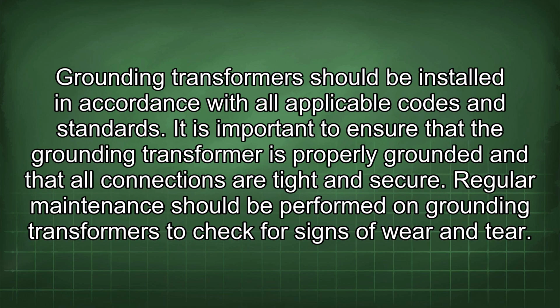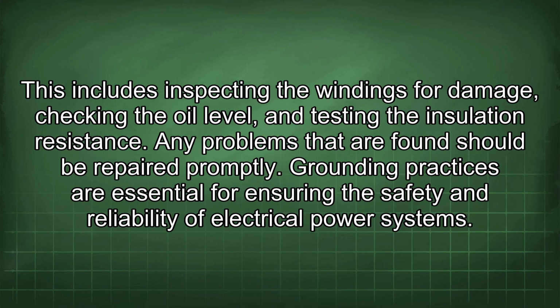Grounding transformers should be installed in accordance with all applicable codes and standards. It is important to ensure that the grounding transformer is properly grounded and that all connections are tight and secure. Regular maintenance should be performed on grounding transformers to check for signs of wear and tear. This includes inspecting the windings for damage, checking the oil level, and testing the insulation resistance. Any problems that are found should be repaired promptly.